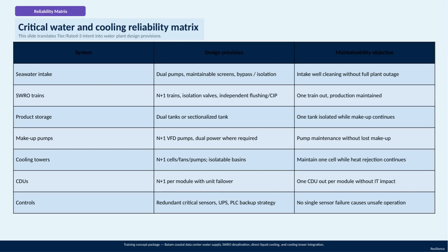Here we have the reliability matrix for the critical water and cooling systems of the Batam Coastal Data Center. This matrix translates the Tier 3 design intent into practical design provisions that ensure the plant remains reliable and maintainable. Starting with the seawater intake, the design includes dual pumps and maintainable screens, along with bypass and isolation capabilities. This setup allows for intake well cleaning without shutting down the entire plant, which is essential to avoid downtime.